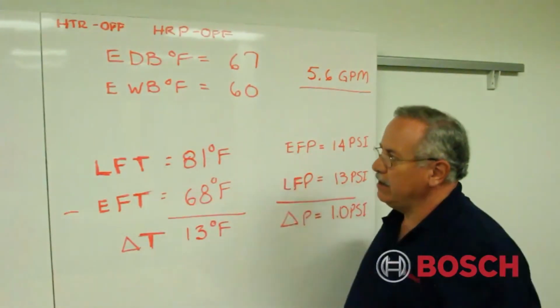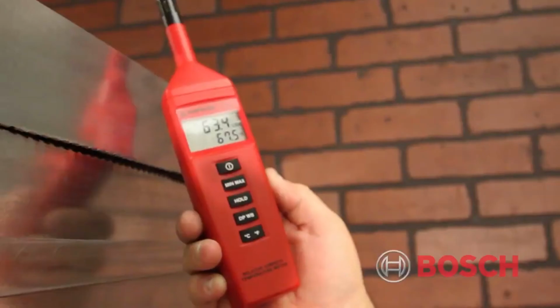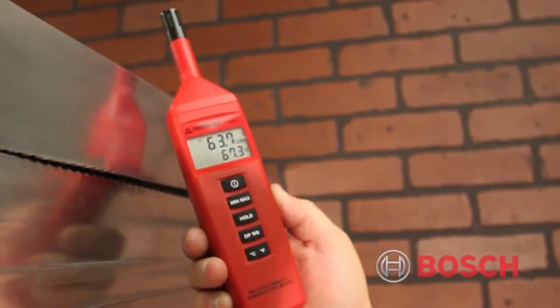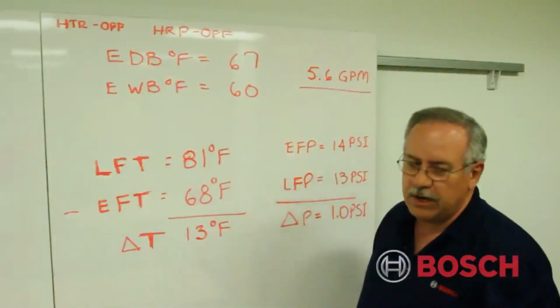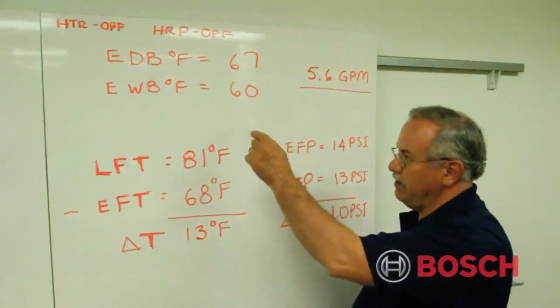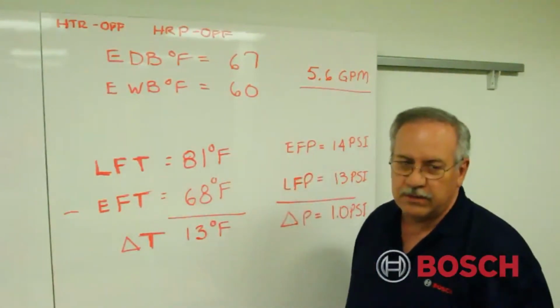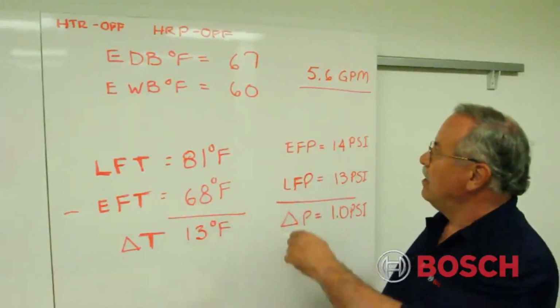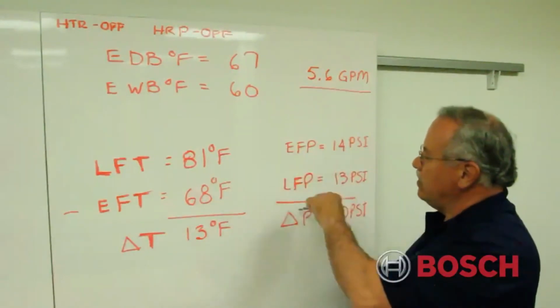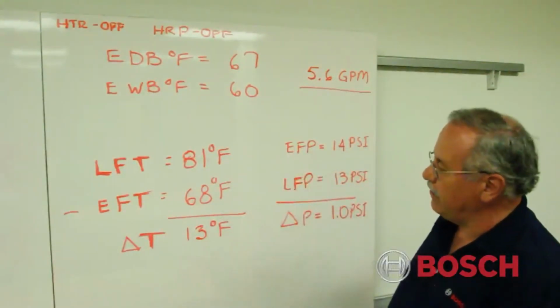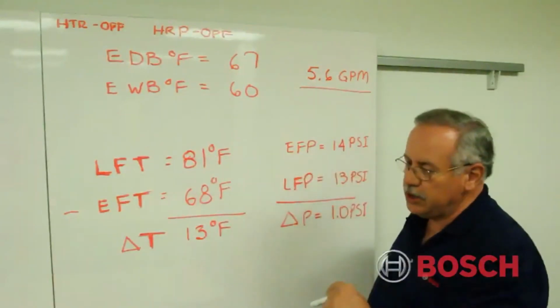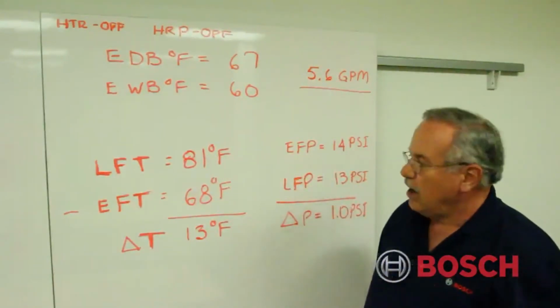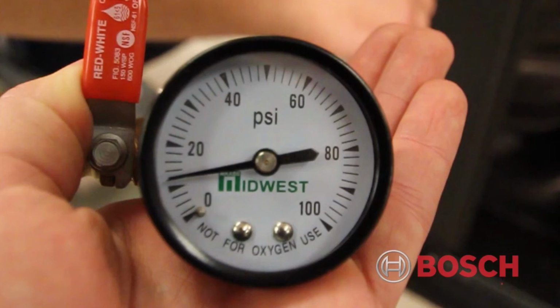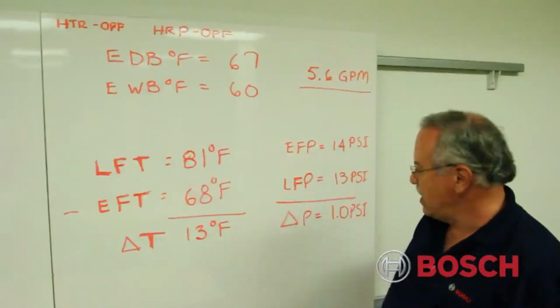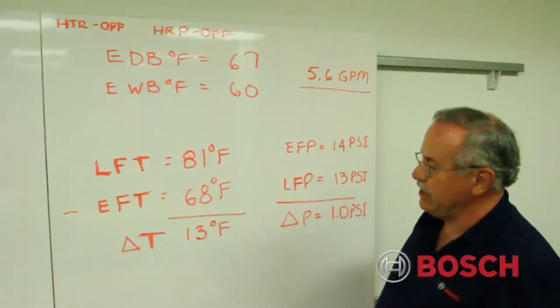Additionally, Mark had to gather the data with a digital psychrometer at the return. He had to determine the entering dry bulb temperature, which he found at 67, and the entering wet bulb temperature at approximately 60 degrees. Then he determined from the coaxial the entering fluid pressure and the leaving fluid pressure of 14 psi and 13 psi, so roughly he found a pressure drop, or delta P, of about 1 psig.